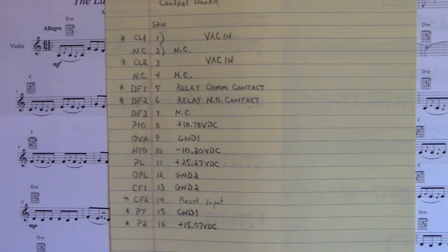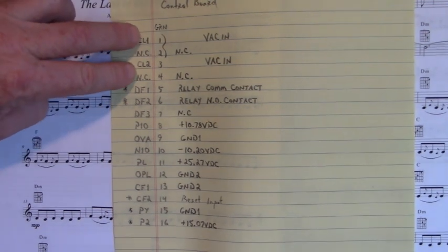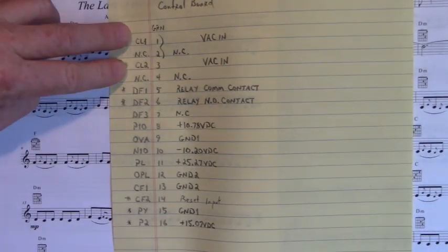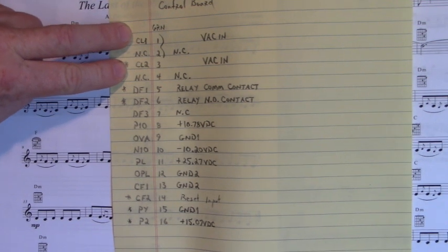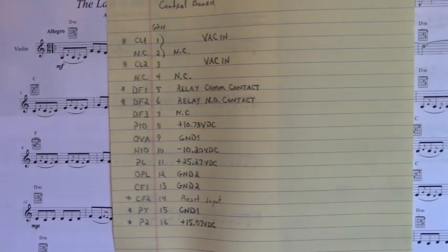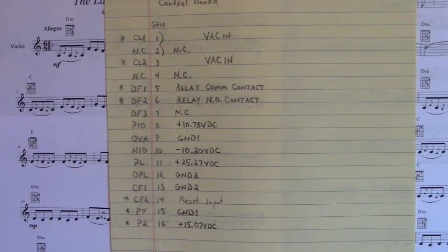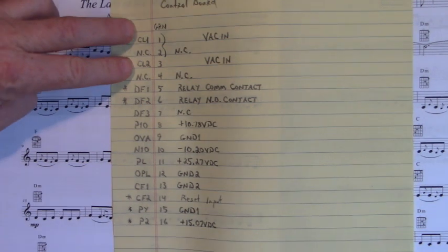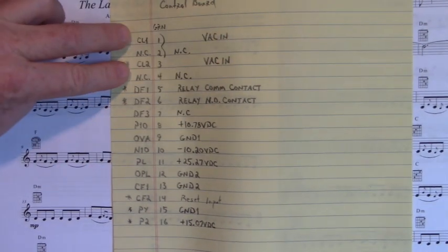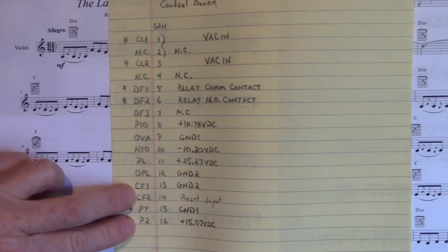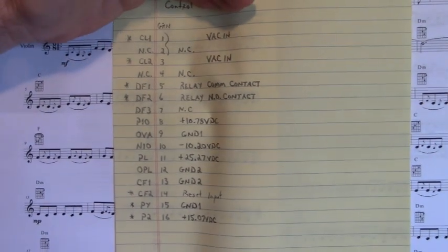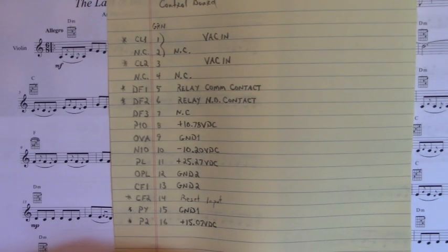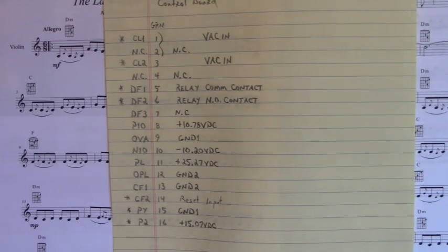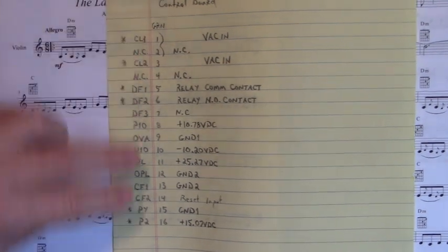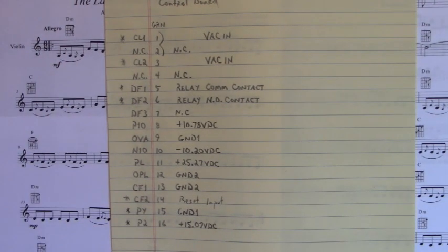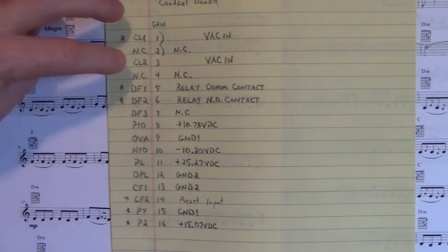Okay. The only thing I got to say about this is be careful up here because I'm really not sure. I didn't want to go above 220 volts AC single phase on pins 1 and 3. Don't get backwards. Don't take and put this high voltage down here. This is the top of the drive. This is the bottom of the drive. Don't put this down here because this low voltage stuff does not like that high voltage stuff.